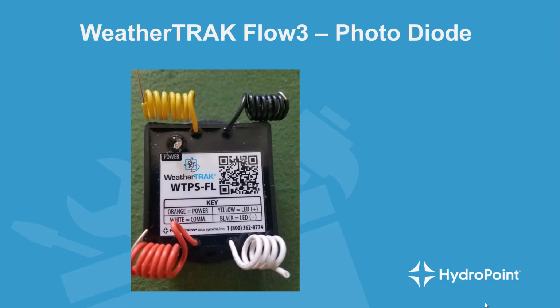Once you've successfully wired the flow sensor into the controller, go back to the valve box and look at your power supply. Look in the upper left-hand corner of your power supply box. When illuminated green, this tells us that the power is flowing from the controller and the signal from the flow sensor to the controller should be live. So the next thing we want to do is prepare the sensor itself. There are a few things we need to check to make sure that the flow sensor will respond when the controller sends it a command.